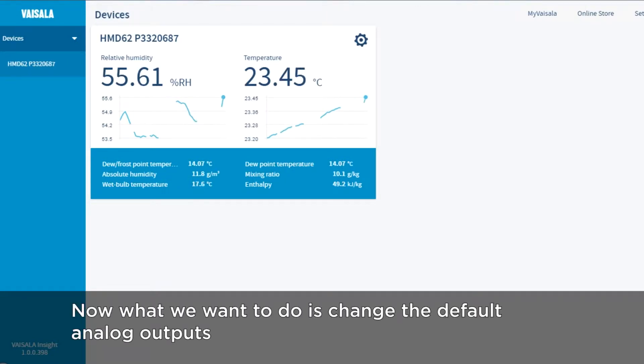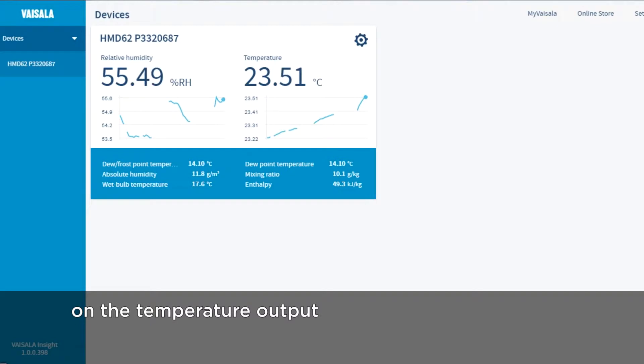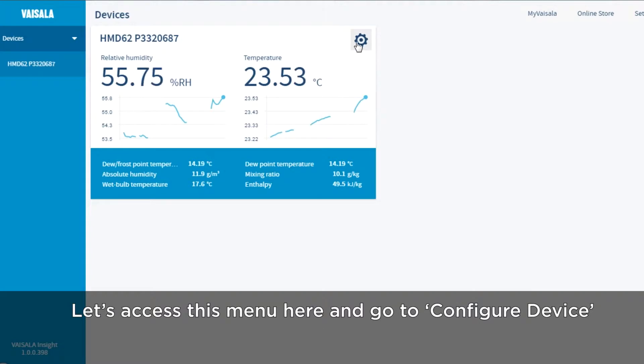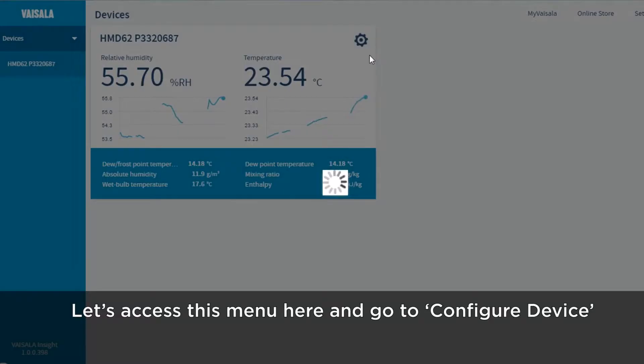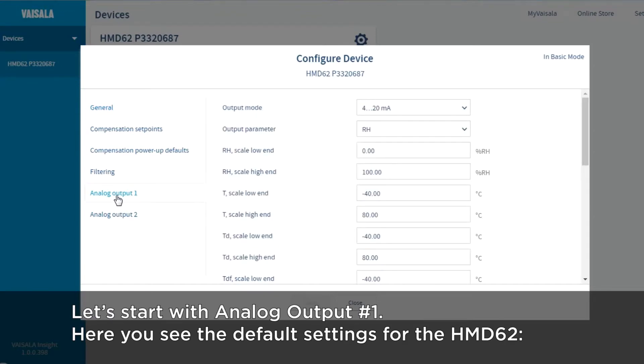Now what we want to do is change the default analog outputs, which is relative humidity for the first output and temperature minus 40 to plus 80 degrees centigrade on the temperature output. We want to have instead dew point and temperature, both scaled from minus 20 to plus 40. Let's access this menu here and go to Configure Device. There are several menus here, but now we want to change the analog outputs, so let's start with analog output number one.